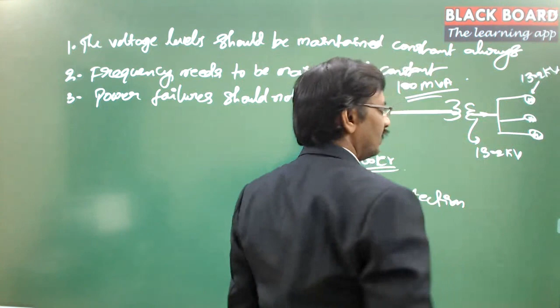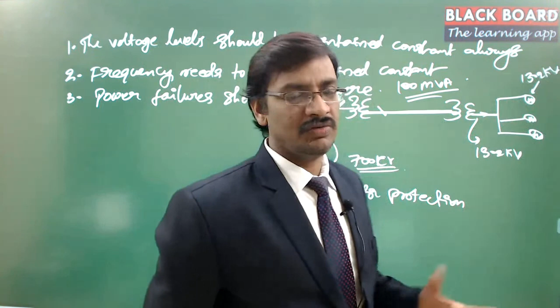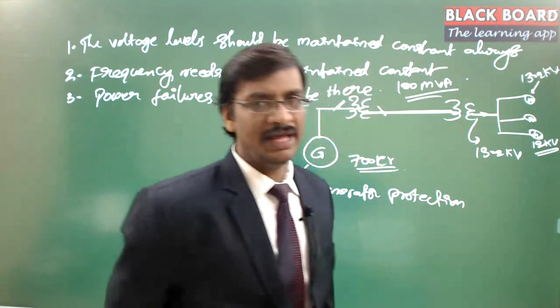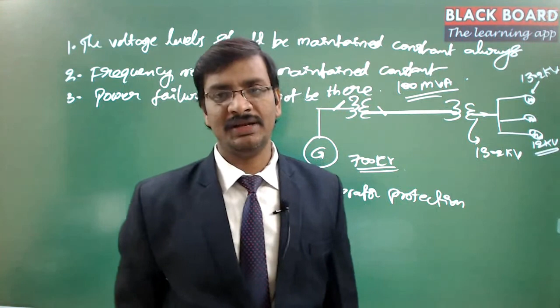Because of the resistance and reactance both, there will be an amount of voltage drop. You are expecting 13.2 kV because these motors are designed for 13.2 kV, but you may only get 12 kV because of the voltage drops in between. Then you might think, why can't we design this motor itself for only 12 kV, so that we know 13.2 kV is supplied here but only 12 kV is coming, and we can design a motor for 12 kV so there won't be any issue in the power system at all?